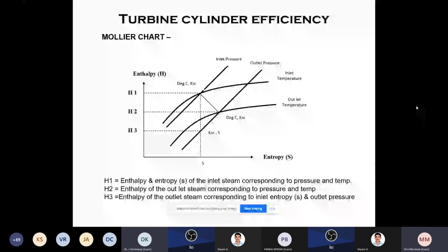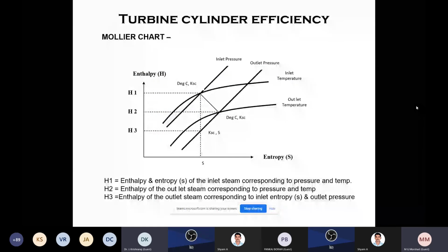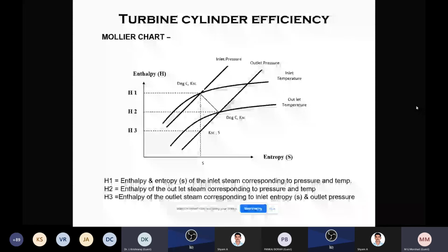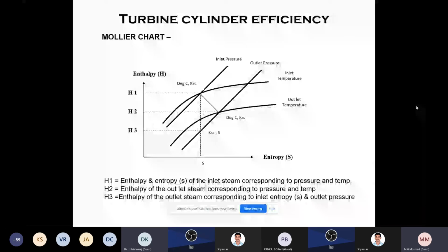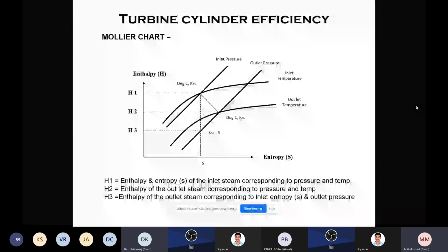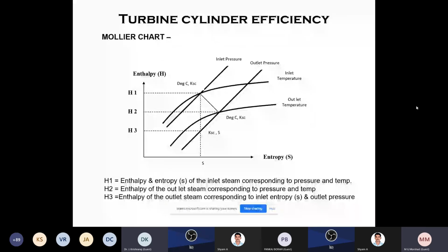Now turbine cylinder efficiency is determined by the Mollier chart. You have to go to the Mollier chart, and the mechanical people, those who are purely mechanical and turbine specialists, can understand these things very well. Heat 1, heat 2, heat 3, these are all the inlet steam pressure and enthalpy of the outlet steam, with its dryness fraction. So these are all the things available. You can go to the Mollier chart, establish it, and understand it better.